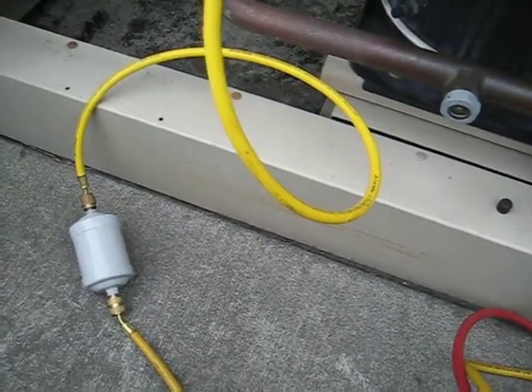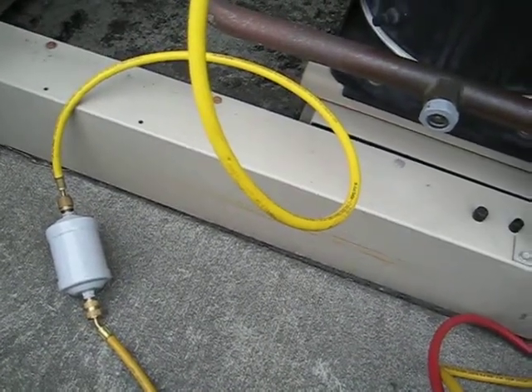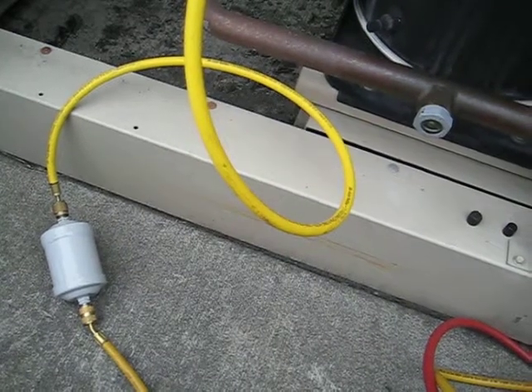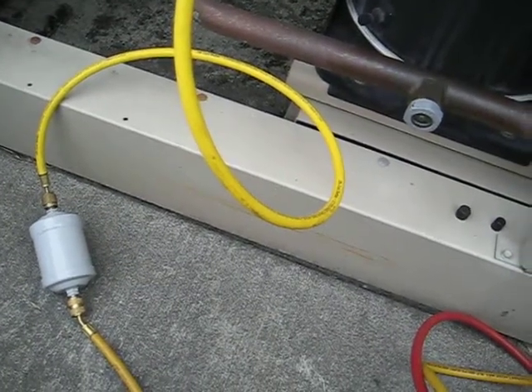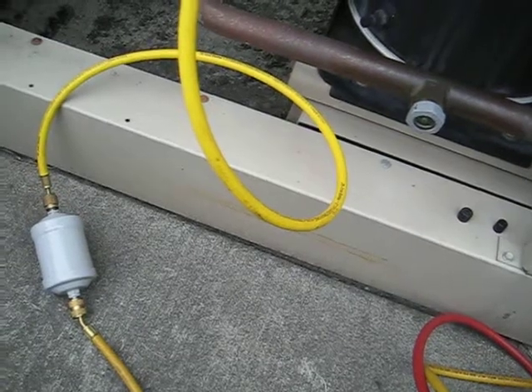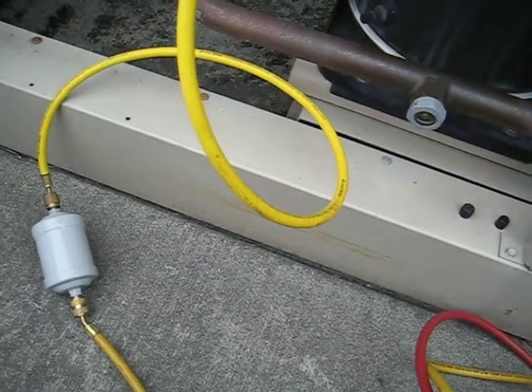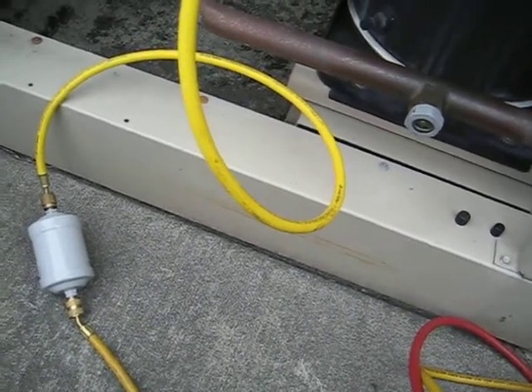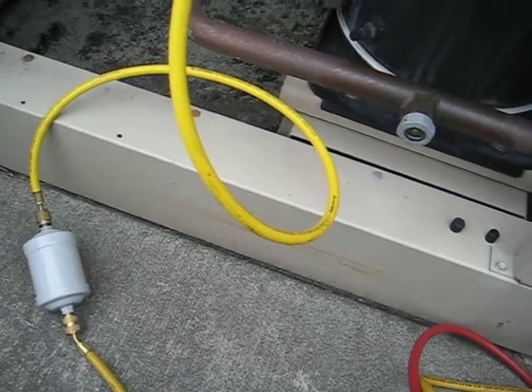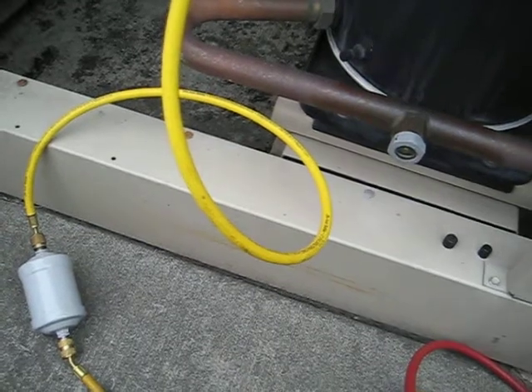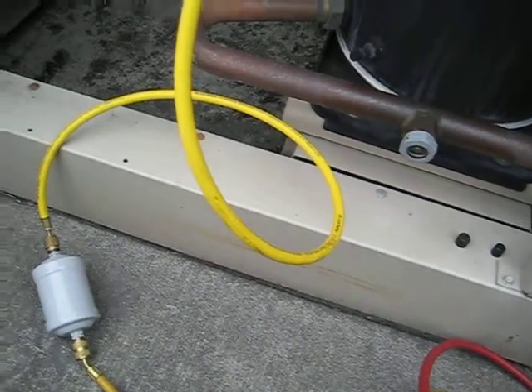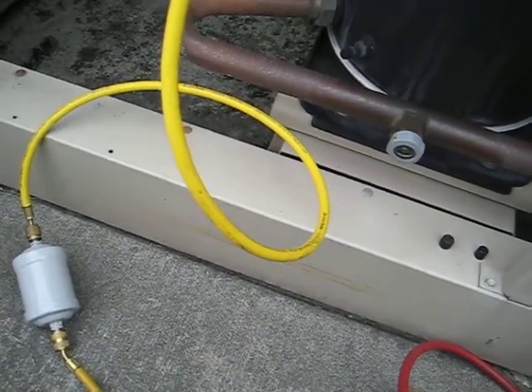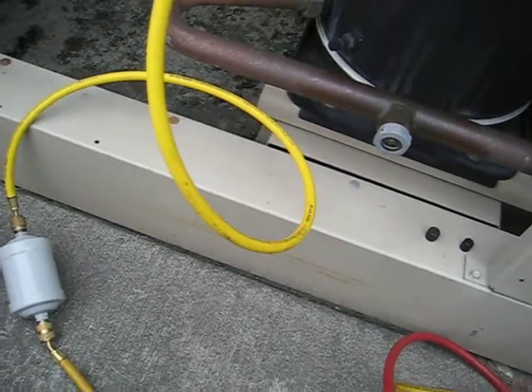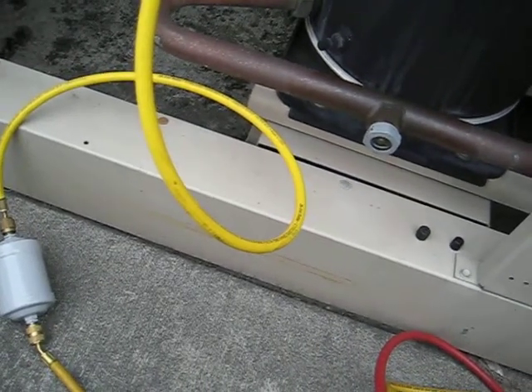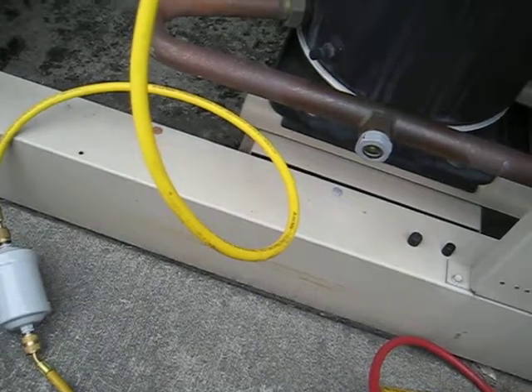And then I'll put my micron gauge on there. A micron is actually 1/millionth of a meter, and it's a 1,000th of a millimeter. It's kind of like when you're checking with a manometer, which usually has some water in it, on a little card, usually with a little hose and some graduation marks. That's for checking atmospheric pressure or pressure inside of a duct which a fan is blowing through. It's not that accurate. But this is the same principle when you use your micron gauge.